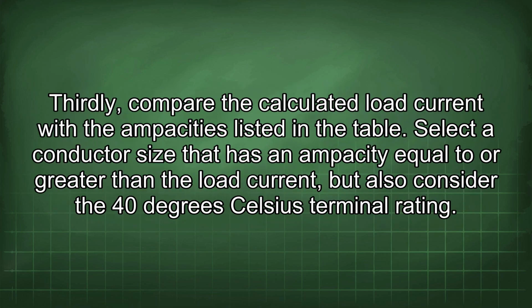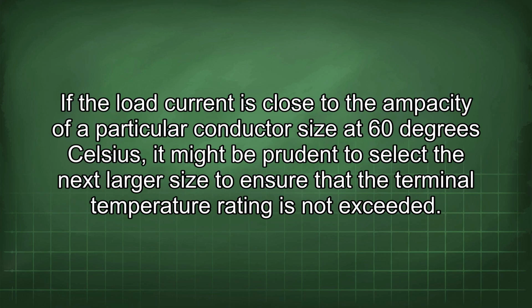Thirdly, compare the calculated load current with the ampacities listed in the table. Select a conductor size that has an ampacity equal to or greater than the load current, but also consider the 40 degrees Celsius terminal rating. If the load current is close to the ampacity of a particular conductor size at 60 degrees Celsius, it might be prudent to select the next largest size to ensure that the terminal temperature rating is not exceeded.